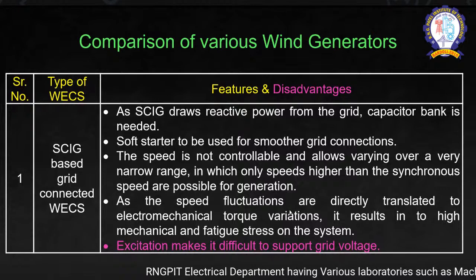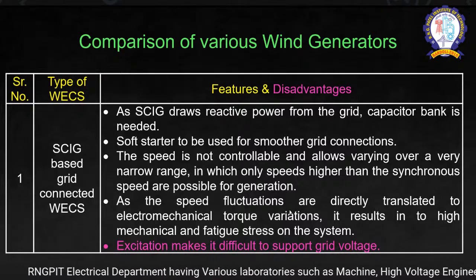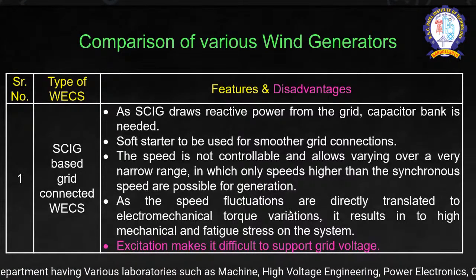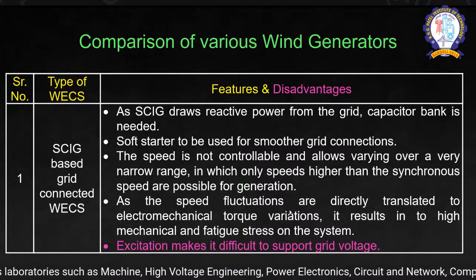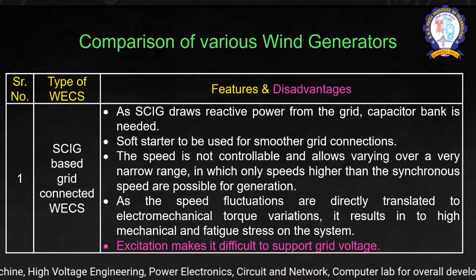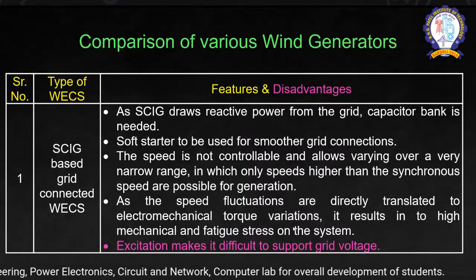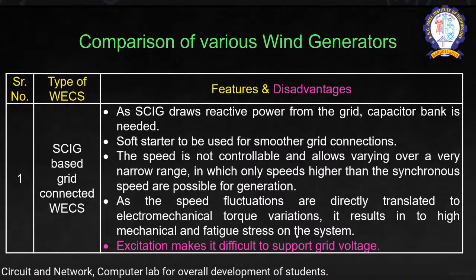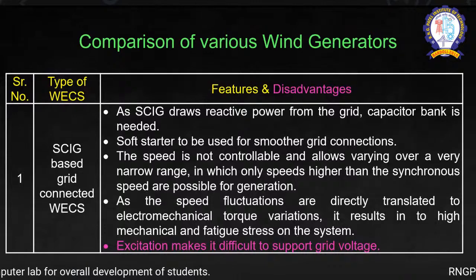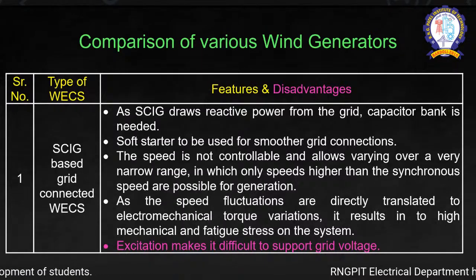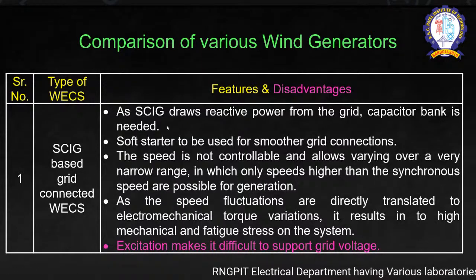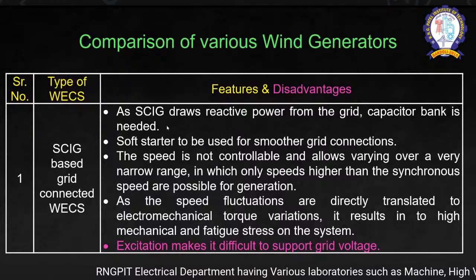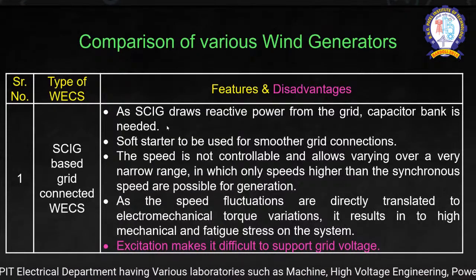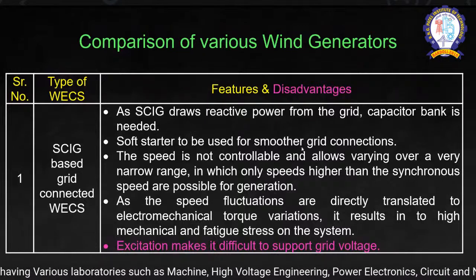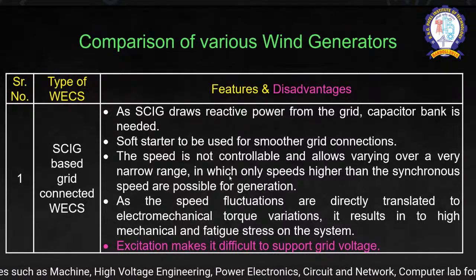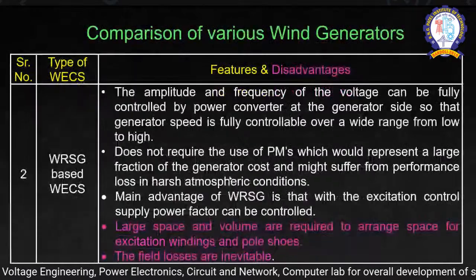Now, this is the comparative analysis of the wind generators. With the lack of time, I am not going to consider each and every point, but I should focus on certain disadvantages or limitations of the squirrel cage induction generator. Its excitation makes it difficult to support the grid voltage. So we need to excite this machine to feed reactive power by incorporating a capacitor bank, because it is not at all a self-excited machine.